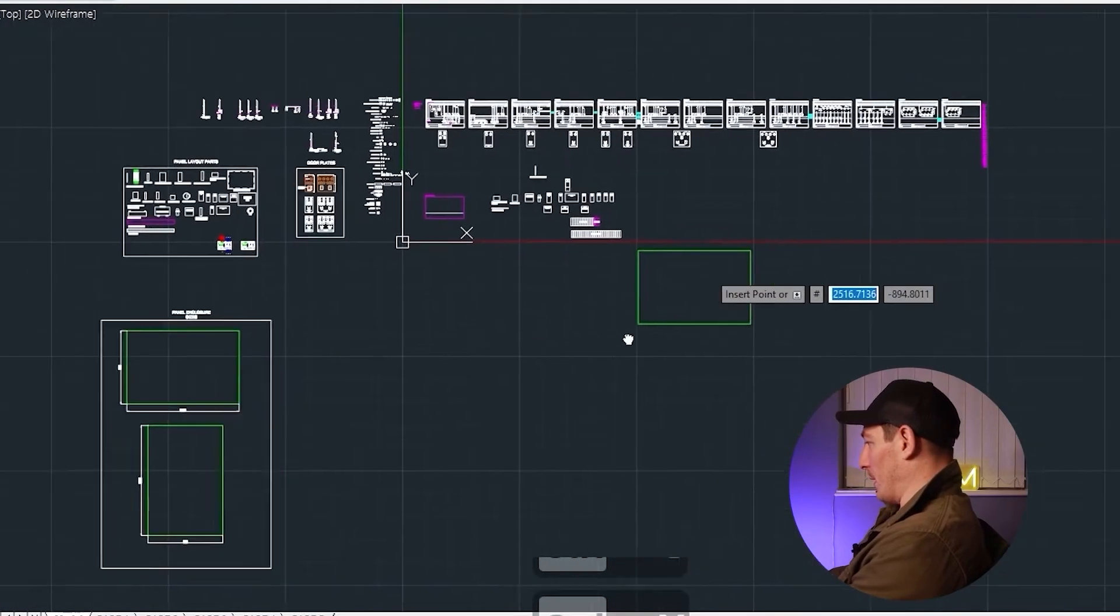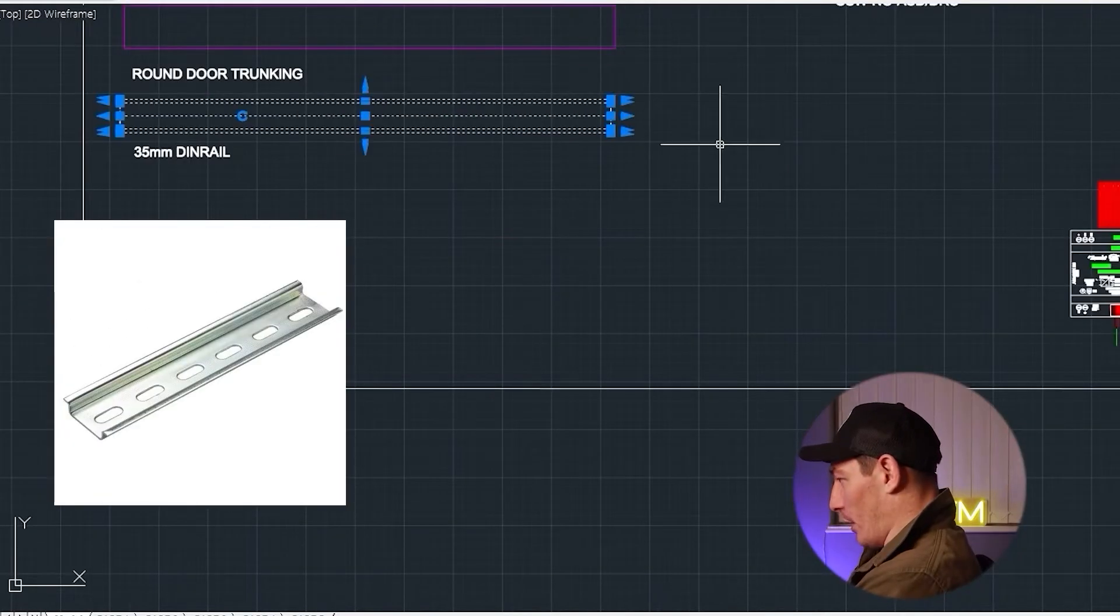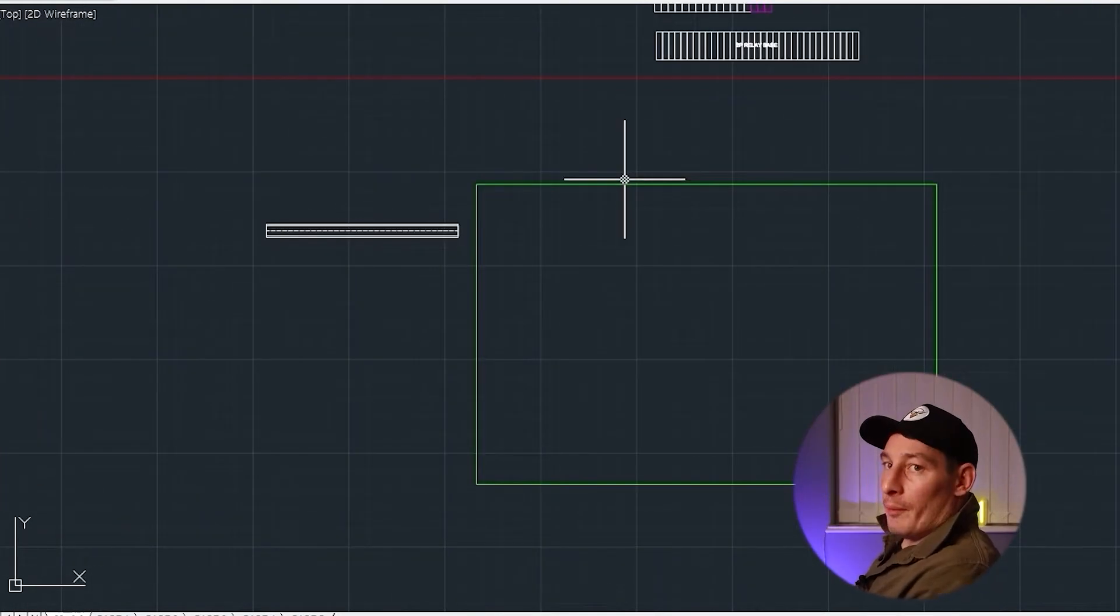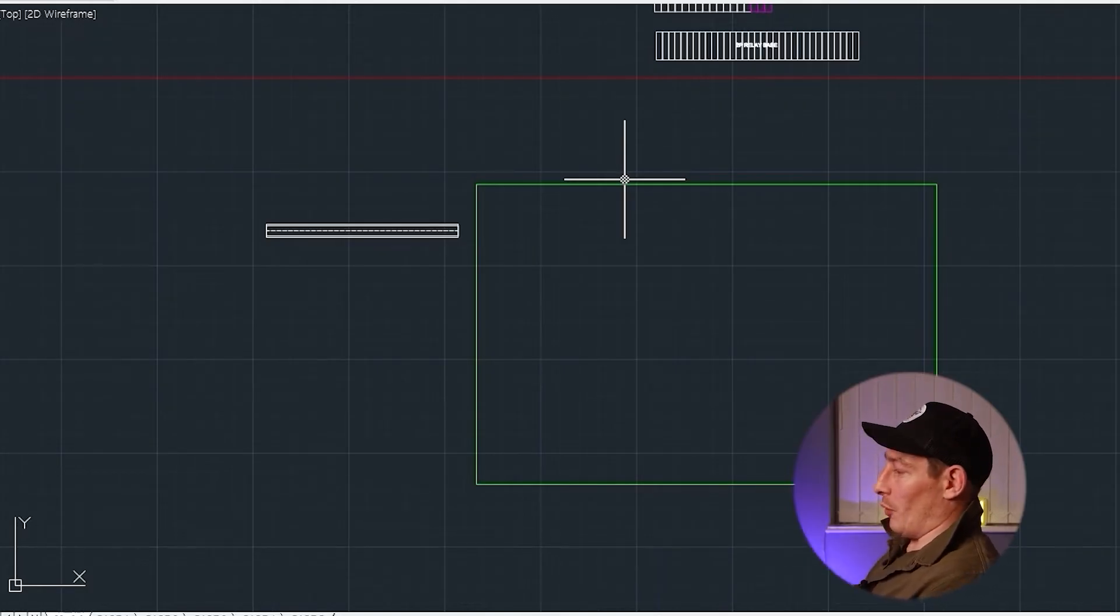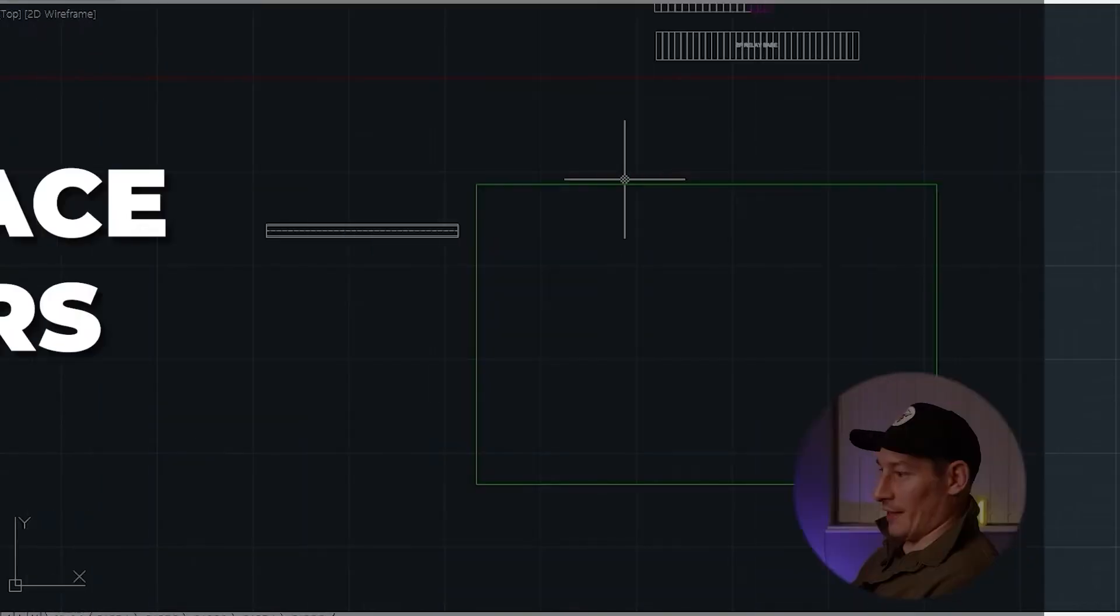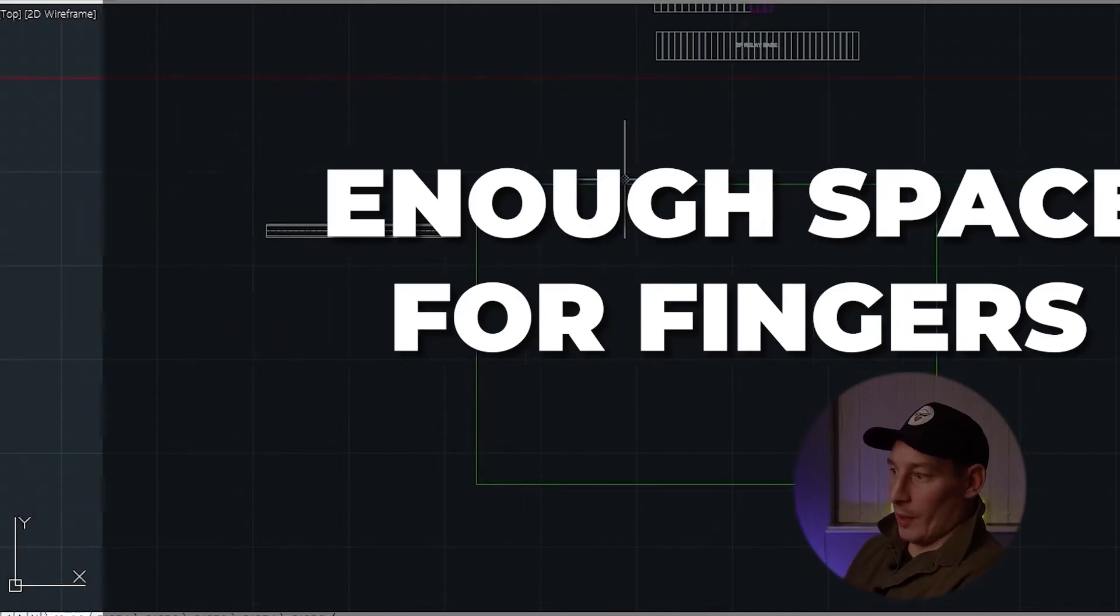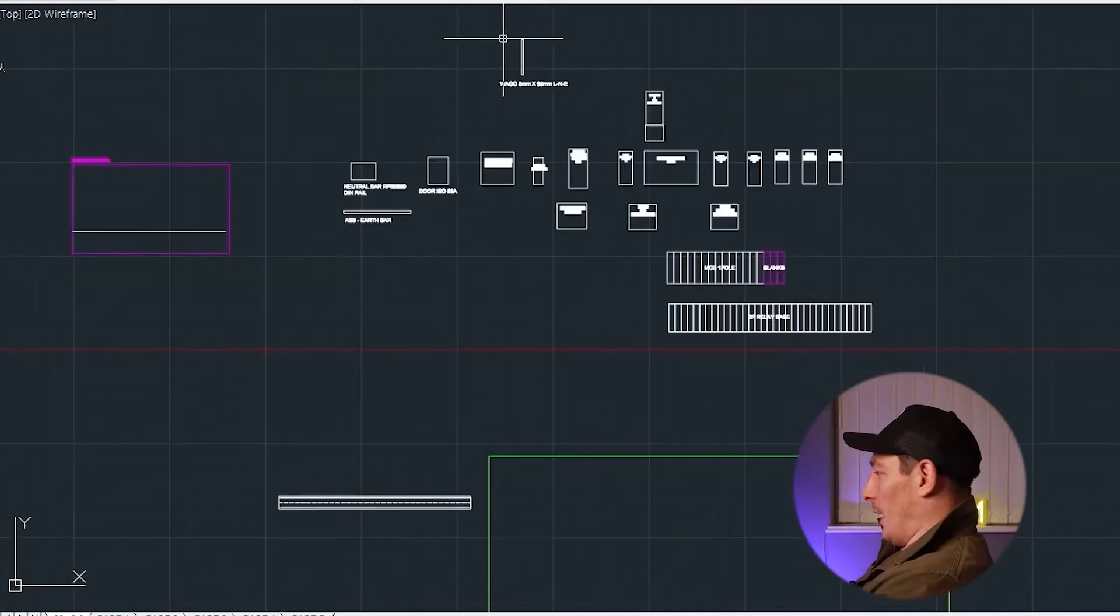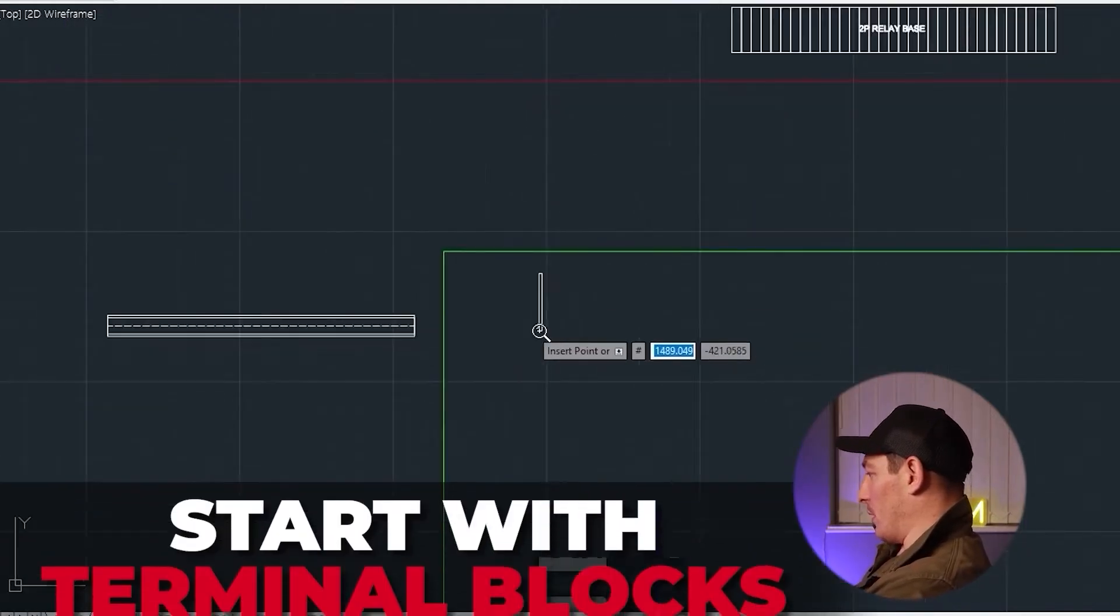It's just really to get an idea of how the components look within that size enclosure. So I'm going to use the horizontal and I'm going to copy that over here. I'm going to grab a piece of din rail and I'm going to start working my way from the top or the bottom depending if it's top or bottom cable entry, and just work out how things look, taking into account spacings of trunking, din rail, and add enough space so you can get your fingers in between the trunking and the modules to actually get the cables into the modules.